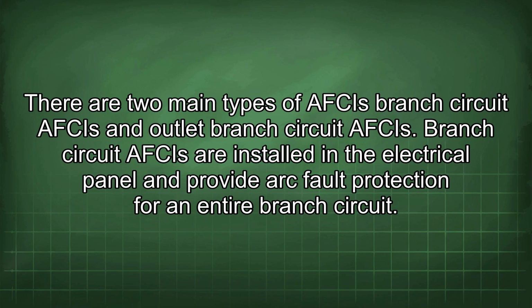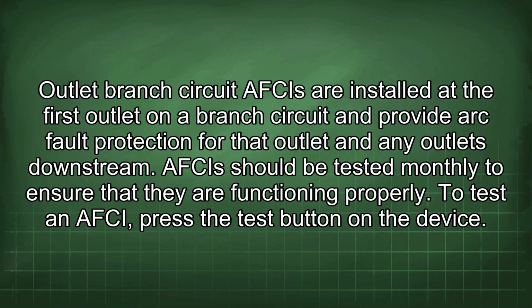Branch circuit AFCIs are installed in the electrical panel and provide arc fault protection for an entire branch circuit. Outlet branch circuit AFCIs are installed at the first outlet on a branch circuit and provide arc fault protection for that outlet and any outlets downstream.